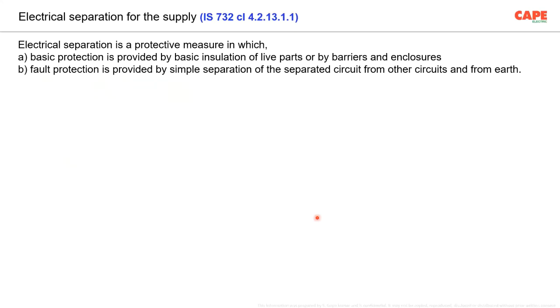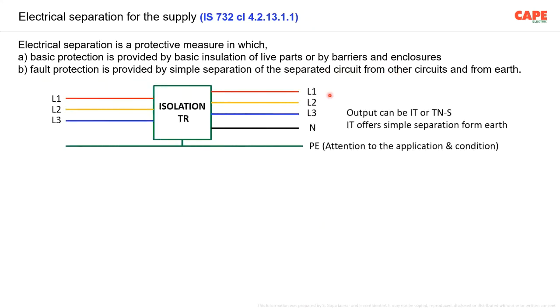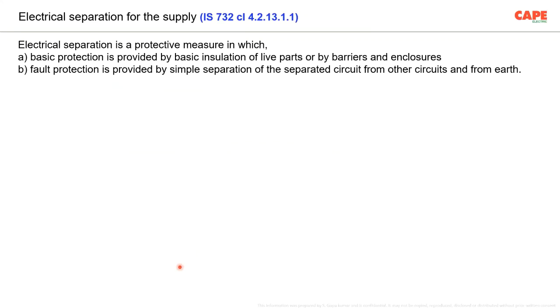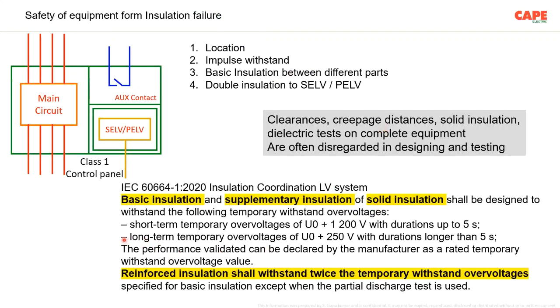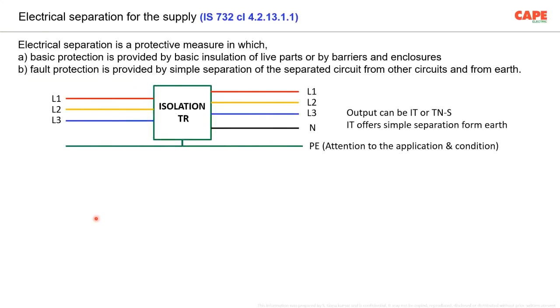Now, electrical separation. Electrical separation is a protective measure in which basic protection is achieved by basic insulation, and fault protection is achieved by simple separation of the separated circuit. Very simple to understand: you have the incoming, you have an isolation transformer, and with the isolation transformer you isolate the secondary side of the circuit. As a result of this electrical separation, a lot of problems existing at the input side of the isolation transformer can be solved at the output side. But as I said earlier, if your equipment withstand levels are unknown to you, then this simple separation also may not work. At the output side of the isolation transformer, for shock protection, IT systems, unearthed systems, are recommended.